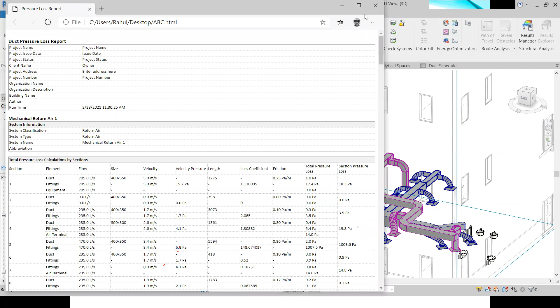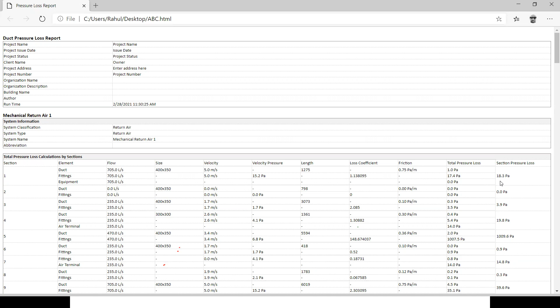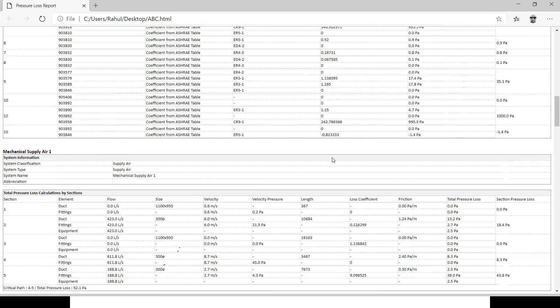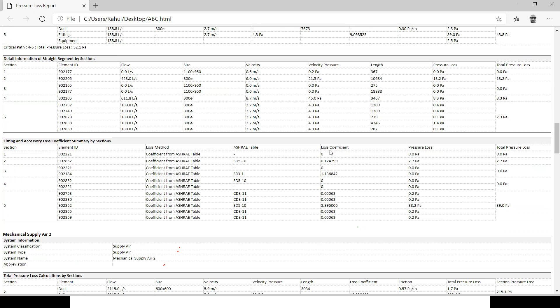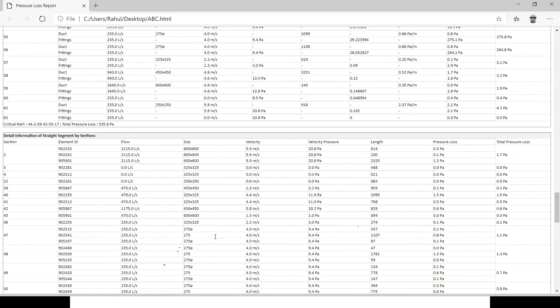So after creating ducts, we can run an analysis and get all the required information like velocity pressure, how much pressure loss will be there, and how much section pressure loss will be there. Everything will be there, and how much pressure loss will be in each fitting. So as per that, based on our requirement, we can manage the drawing or change the drawing. And one more major advantage is that everything will be based on the selected standard. So here we are using the ASHRAE table. As I told you, we design based on different standards like ASHRAE, Carrier, etc. Here we are using the ASHRAE table, so based on the ASHRAE standards, all the data are available for the duct design.